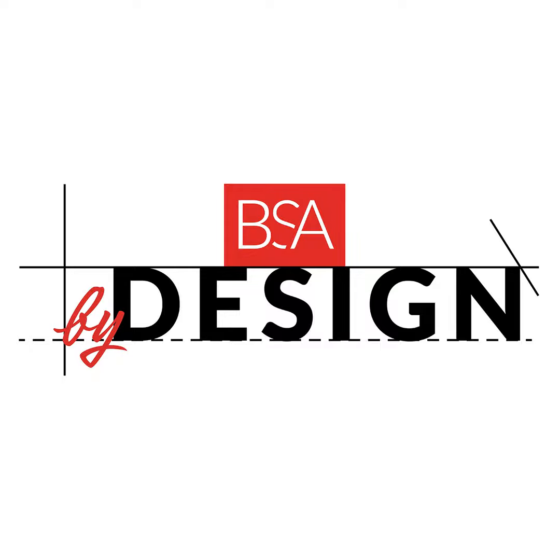Okay. I totally agree with Matt that prefab is kind of where everything's going, the more that they can build off-site and bring in and kind of put in place. And I think there are advancements that are happening within that too. There've been prefabbed head walls around forever. At a conference last year, I was looking around, and one of the manufacturers had ways that you could easily just, the facilities guy could take off the panel, route out a hole, and put in another med gas outlet, which really increases Matt's flexibility that he's been talking about.